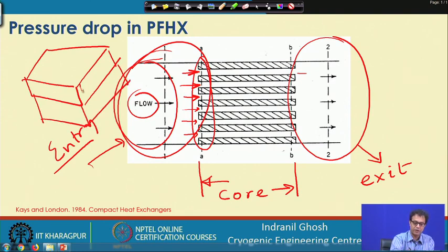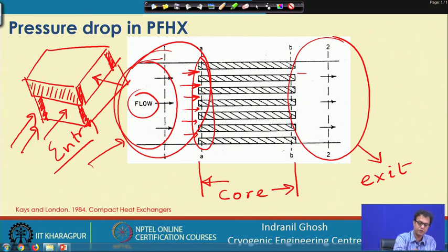So, if it is a plate fin type exchanger, cross flow type, this is the side bar for this fluid flow, and similarly for this side you can see that this is the sidebar. So, when this flow is taking place from this end, you will find that this sidebar is blocked for this flow. So, this flow can take place only if we take this as the frontal area, we will find that almost 50% or some portion of the fluid flow area is blocked for this fluid.